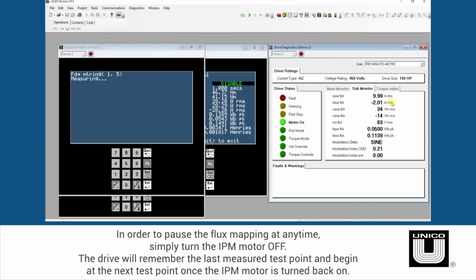In order to pause the flux mapping at any time, simply turn the IPM motor off. The drive will remember the last measured test point and begin at the next test point once the IPM motor is turned back on.